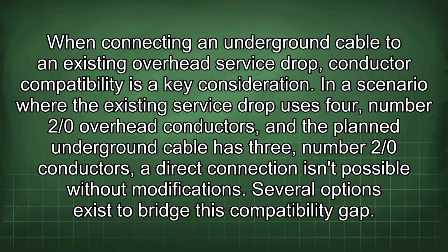When connecting an underground cable to an existing overhead service drop, conductor compatibility is a key consideration. In a scenario where the existing service drop uses 4 2/0 overhead conductors and the planned underground cable has 3 2/0 conductors, a direct connection isn't possible without modifications. Several options exist to bridge this compatibility gap.